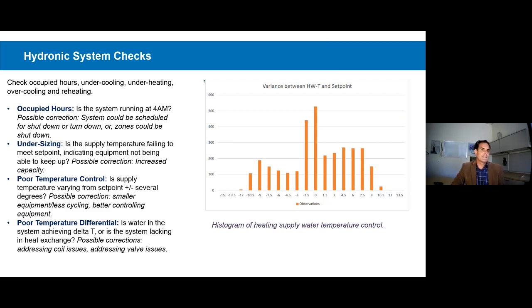Anytime we look at an existing system, we face a choice as designers. Are we going to keep this or are we going to change this? If this variation in supply water control is acceptable, then we would base our new design around a system that has that much variation in it. If this variation in water temperature is not acceptable, then we need to deliberately do something to change it.